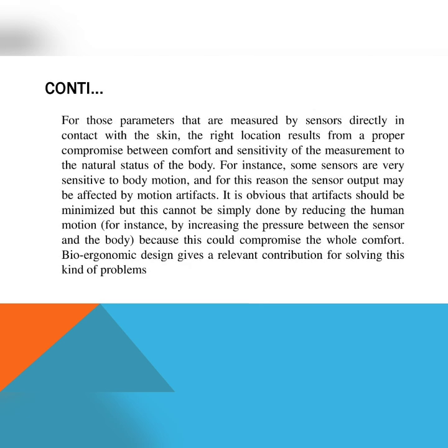For parameters measured by sensors directly in contact with the skin, the right location results from a proper compromise between comfort and sensitivity of the measurement to the natural status of the body. Some sensors are very sensitive to body motions, and for this reason the sensor output may be affected by motion artifacts. Artifacts should be minimized, but this cannot simply be done by reducing human motion — for instance, by increasing the pressure between the sensor and the body — because this could compromise comfort.